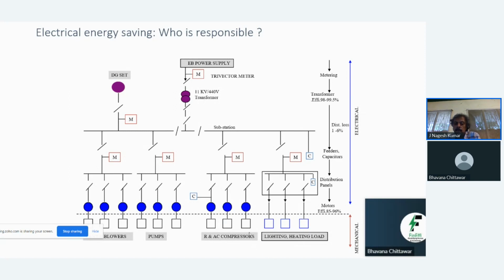That ultimate user, the production man, decides how much energy will be demanded from the compressor. The quantity of air and the pressure at which he's using it will decide the power required for the compressor, which in turn decides the power drawn from the motor. So when you want to save electrical energy, it's not the electrical engineer's job to arrest leakage - it's the maintenance person. When he arrests the leakage, there's a reduction in electrical energy. And if a process man is confident of using the compressor at lower pressure, then electrical energy is saved - it's not the electrical engineer who is saving it.